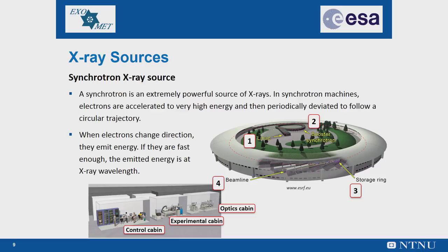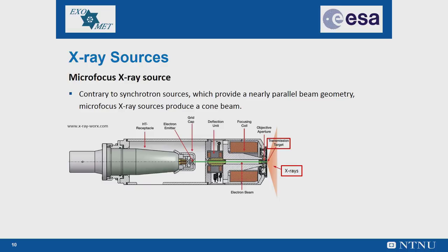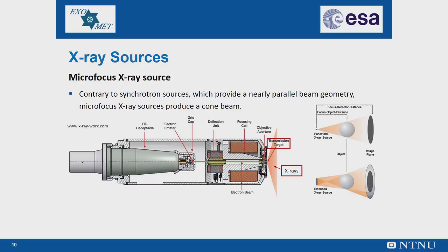Contrary to synchrotron sources, which provide a nearly parallel beam geometry, micro-focus X-ray sources produce a cone beam. The most important parts of the micro-focus X-ray source are the transmission target and the focal spot, or source size. A focused electron beam strikes the transmission target. Depending on the specific application, transmission targets can be made of different kinds of materials, thus selecting a specific X-ray emission spectrum. The size of the focal spot defines the sharpness of the resulting X-ray image; the bigger the focal spot, the higher the geometric unsharpness, meaning that high-resolution X-ray analysis requires an appropriately small focal spot.